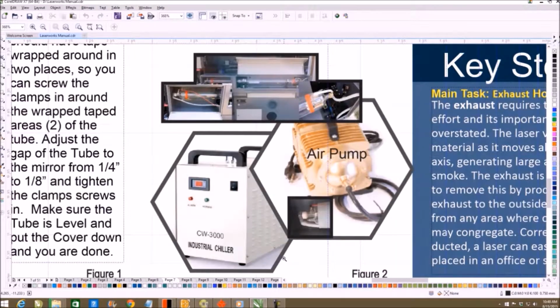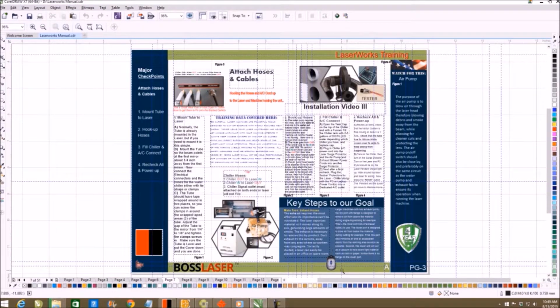So as you take it out, I want you to look at the back of the machine. I want you to look at the tube. I want to verify the tube got there in one piece. This is why we're very careful on taking it off the pallet with the rail, and that the connections are made. Now, a lot of times the connections are slide-on connections, and you may have to retighten them. But normally they're fine. Maybe 1 out of 100 we might have an issue with. And so when you're looking here, there's the connection I'm talking about right there. Screws onto the post, done. Okay, very, very important.